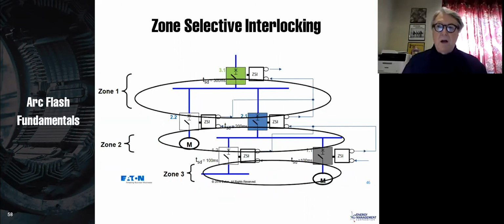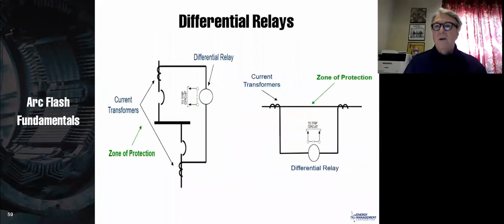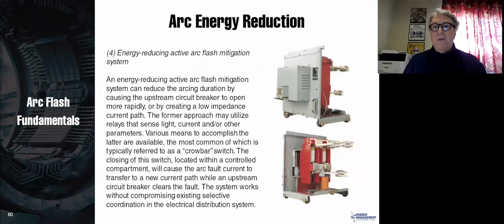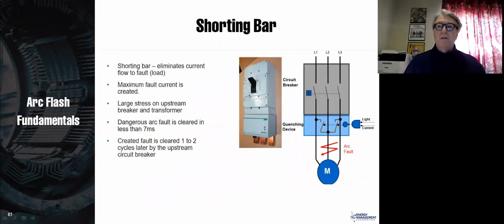Here's zone selective interlocking. That certainly is a way of having your cake and eating it too, as they say. So you can have your short time delay, but in these zones, if you have zone selective interlocking, it can trip instantaneously. Differential relays, the same thing. These tend to be expensive, but they can provide quick trips. This is a shorting bar. Whenever you have a high current, this thing actually shorts on the primary of the breaker and causes a very high current to flow, in addition to extinguishing the arc fault because you've just shorted this current here. Never seen one of these in practice, but they do exist.